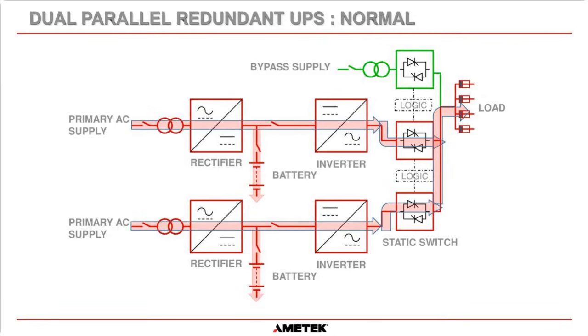So that was a commercial UPS versus an industrial UPS. Now I want to talk about the different ways that you can connect UPSs. Obviously, you can have a single UPS like we just showed you in the slides before. But the other thing you can do is have a parallel redundant UPS. That means you connect two UPSs together on the output of the system, in parallel. That's what this drawing shows you here.